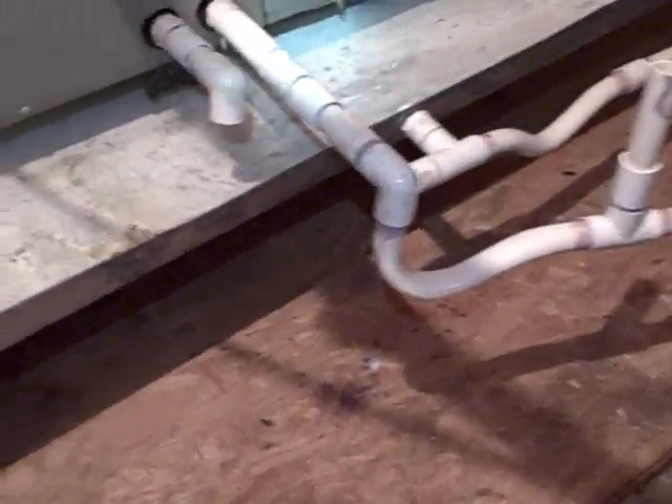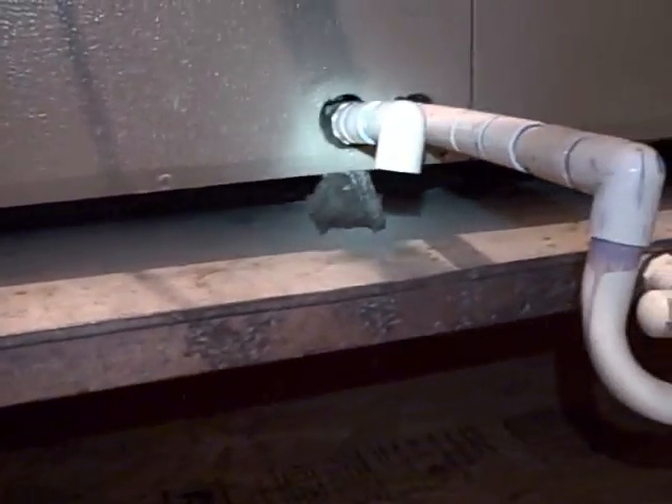Primary drain. It's got a riser on it. The secondary looks kind of high. Looks like the water's been dripping — running down into the duct there, soaking in and dripping off. So I wonder what's going on here. Let's take the case cover off and see if I can figure out what's going on.